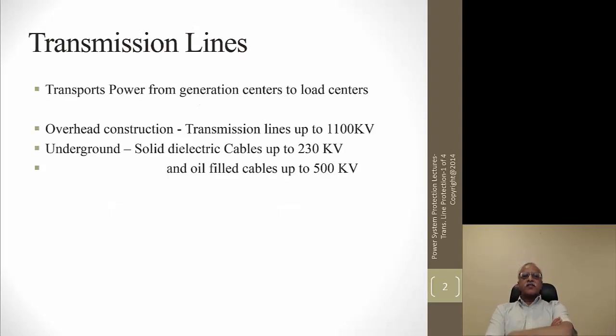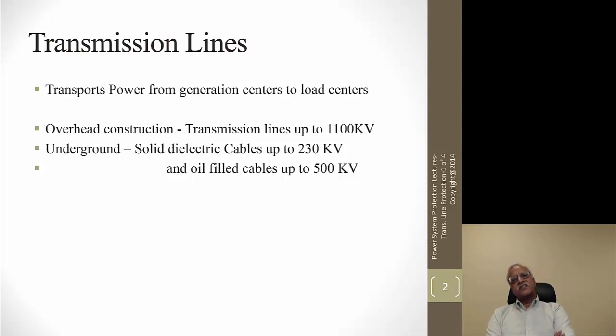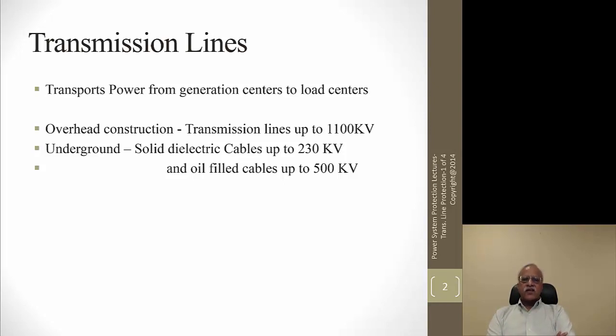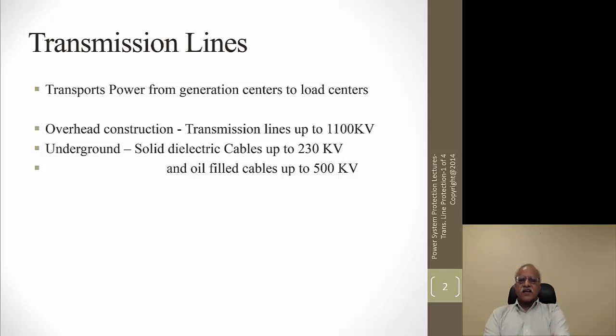Transmission lines transport power from point A to point B — point A being the generator or generation center, and point B being the load center. Normally generators produce power at up to 26 kV with up to 1000 megawatts. You step up the voltage to reduce current, since power is voltage times current, allowing the same power to be transmitted with less current-carrying conductors.